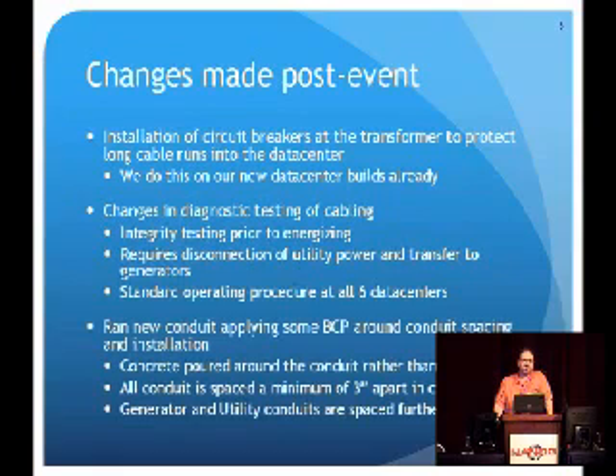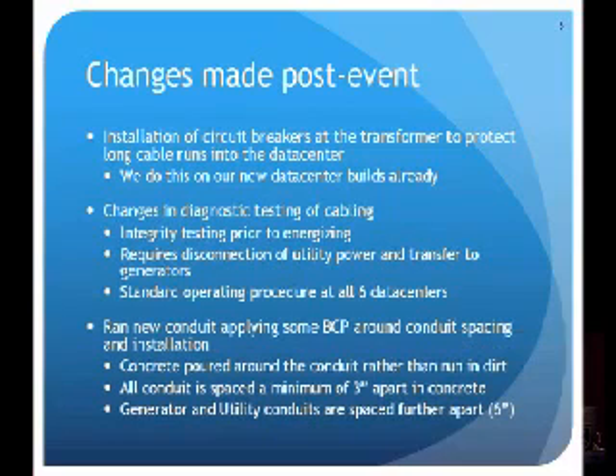In reconstructing this particular data center, we actually ran new conduit, applying some best practices around the spacing and the installation. The original conduit was actually kind of piled on top of each other in dirt without any concrete poured around it. So we actually spaced it - it's a minimum of 3 inches apart now with concrete poured around it. And we spaced the generator and the utility conduits further apart from each other.